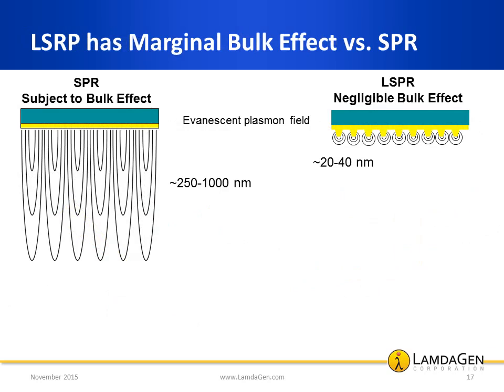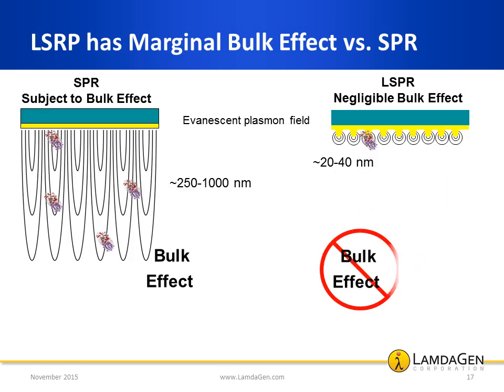A second key difference between SPR and LSPR becomes particularly notable in biosensing applications: the sensing volume of their respective plasmon fields, captured by what is referred to as the bulk effect. Due to the much larger plasmon field of SPR — up to 1,000 nm versus LSPR's 40 nm — biomolecules not actually bound at the sensor surface can be detected in SPR, causing a bulk effect or false positive reading, as depicted by the three unbound biomolecules shown in the sketch. In contrast, in LSPR, only molecules bound at the surface are captured by the localized plasmon field; the others are invisible to the sensor and do not contribute to the signal. Thus, LSPR has marginal bulk effect.